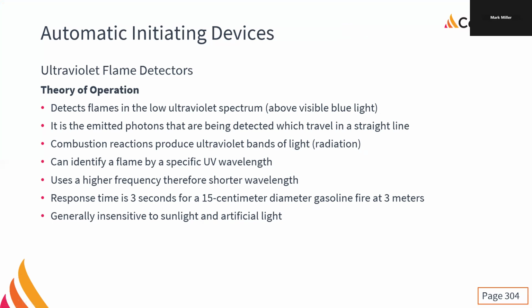But we've had repeated issues with the two flame detectors at the hangar door end, the giant opening wall to let the planes in. They kept going into trouble. Now, it wasn't a sunlight issue, they're pretty insensitive to sunlight. We think it was a temperature issue, because it was going into trouble in the middle of winter, and when it's that cold, we think it was causing issues.